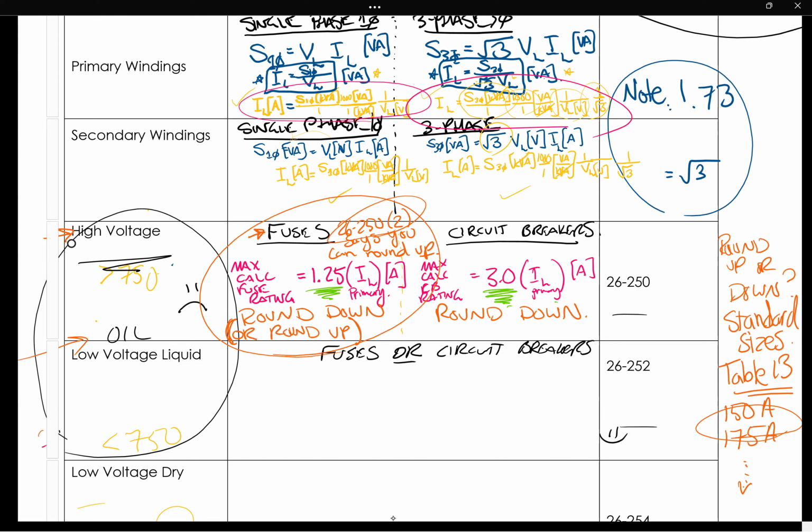Why would you want to round up? Round up if you're going to nuisance trip. If you have a special case where it is safe to round up. If you have to round up. But usually you'll round down.